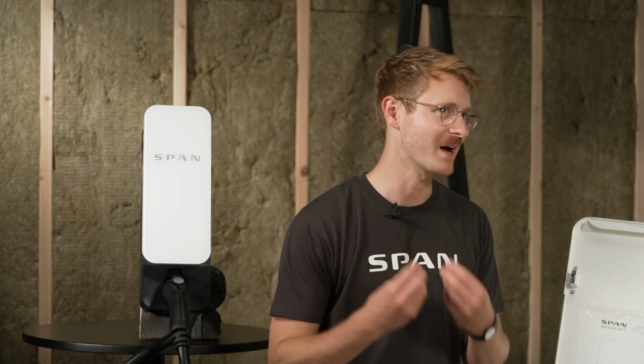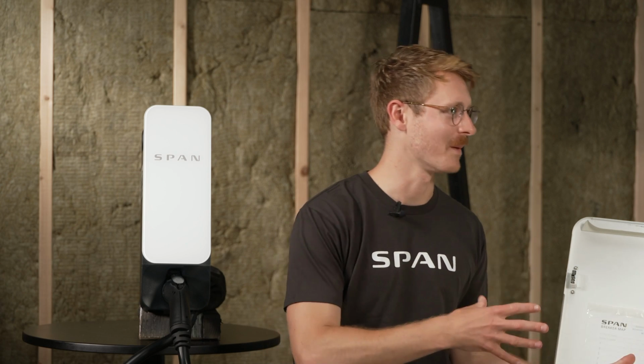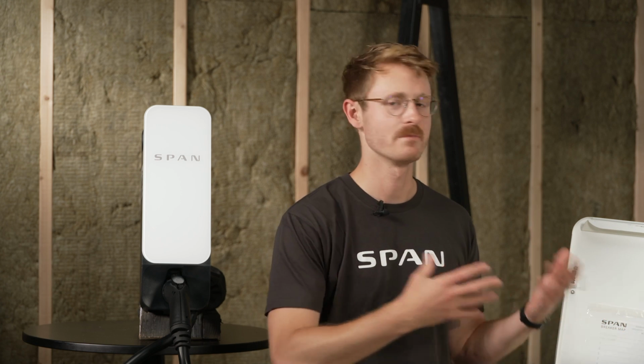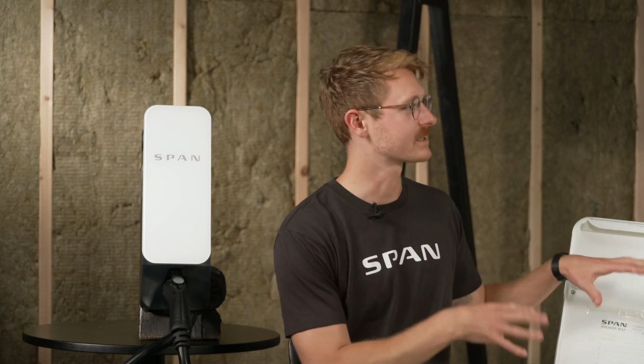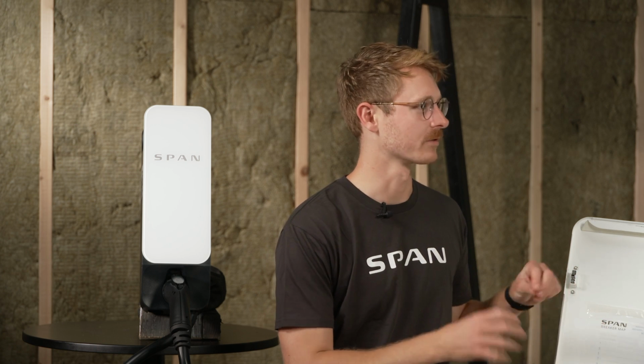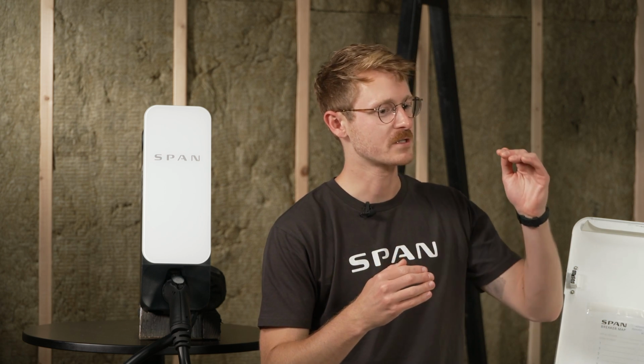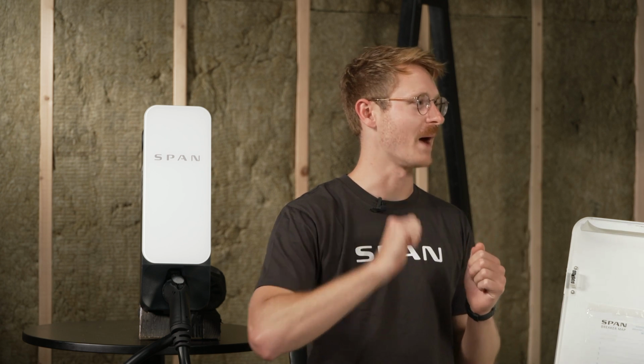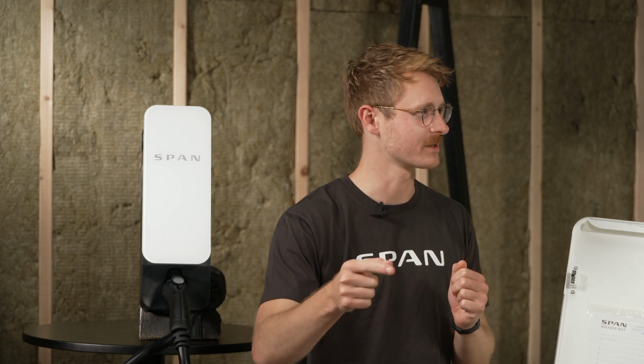This comes back to a theme of flexibility - just like with backup, we want to give the homeowner the most possible within safe and reasonable limits. So in that situation, maybe it's a 100 amp service - rather than getting the 20 amp or 16 amp EV charger, you can get a full 48, and this system will monitor in real time what's coming in through the service feeders and start to throttle back what the car is charging.